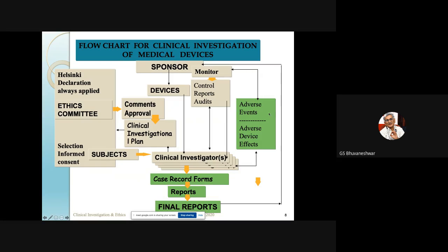And then the monitor also follows up on all adverse events or adverse device effects. Adverse events may be device related or may not be device related. So he'll keep the sponsor and the ethics committee informed about all these adverse events. It's also the responsibility of the clinical investigator to keep the sponsor and, if necessary, the ethics committee informed about adverse events, particularly if the risks are suddenly high and the adverse events need to be looked at very seriously.